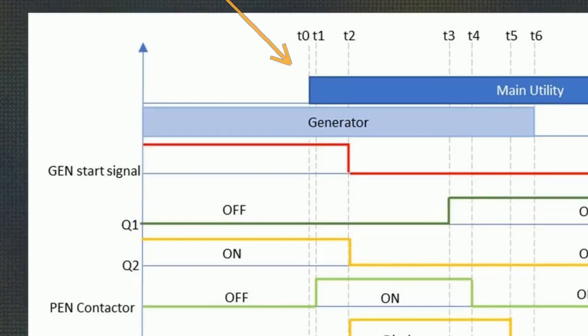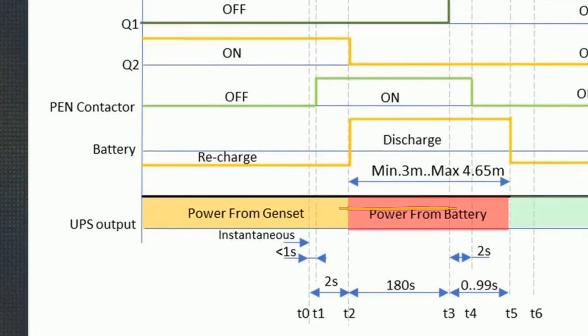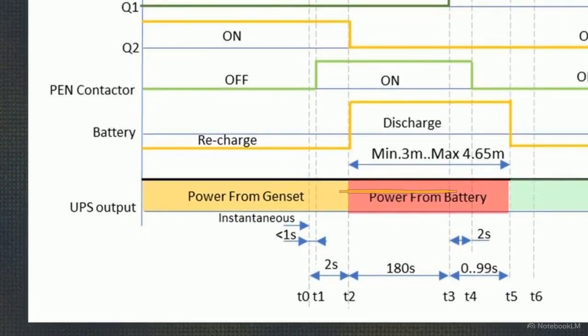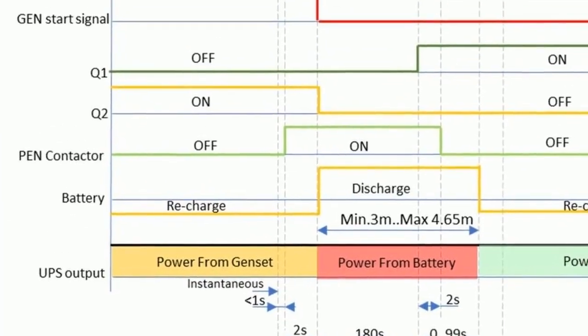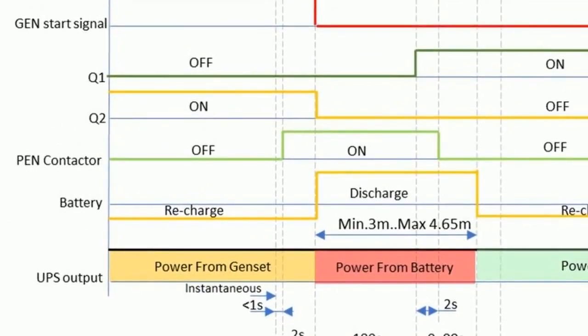Eventually, the utility company restores power to the grid. However, the ATS does not immediately switch the load back to source 1. This chart illustrates the restore sequence. To prevent dumping the facility onto a volatile feed, the system enforces a return stability timer to prove the grid is stable. Then, Q2 opens. The UPS bridges the gap, the PEN contactor cycles, and at T3, Q1 closes.